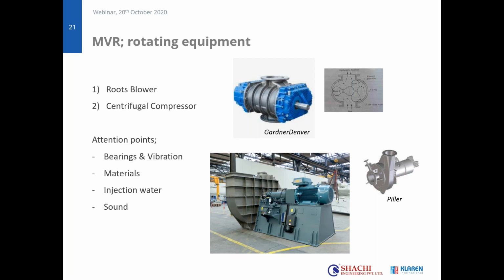One thing which I forgot to mention is that in both systems you would need injection water to desuperheat the vapor. So at the end, the vapor coming out of the MVR compressor is superheated, and you would want to lower the temperature. And in the case of the roots blower, you also need to cool the block. The housing will get heated up by the inefficiency of the blower, and you need to cool this by injecting more water than you would normally expect for de-superheating. But I'll show you later, that will also give you an advantage. So this is the first key element: we talk about rotating equipment and we need to take care of this.